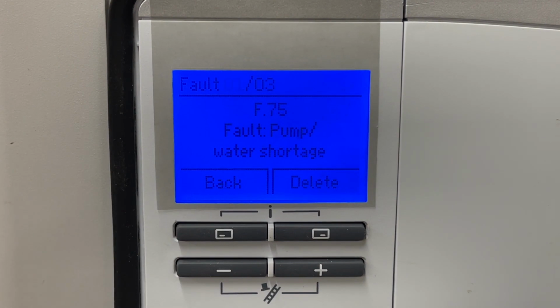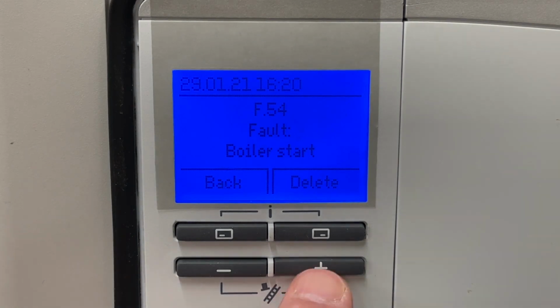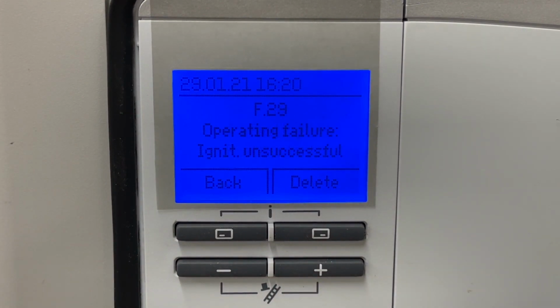So if we look at that one, it says pump failure or water shortage. That was when I unplugged the pump. If we look at the next one, the other fault here was a start, F.54, so we need to look in the boiler and see that it's giving us the times and everything. And then the last one here was failed to ignite, and that's because I turned the gas off, and that's a very popular one. Lack of gas pressure is the most popular one.